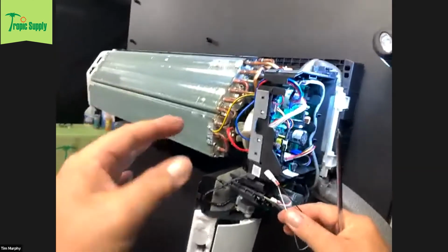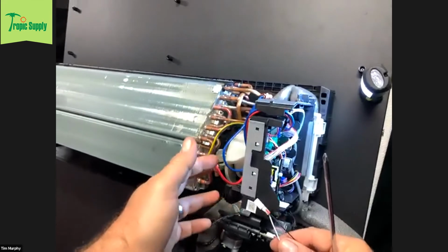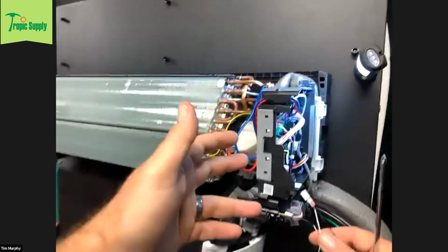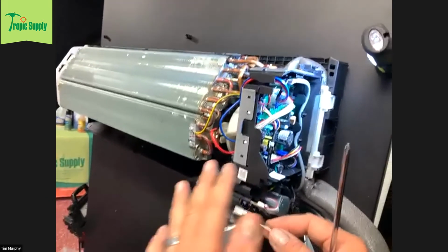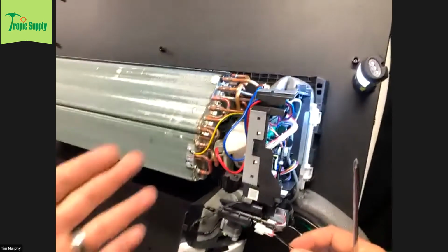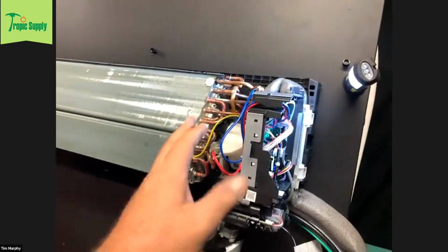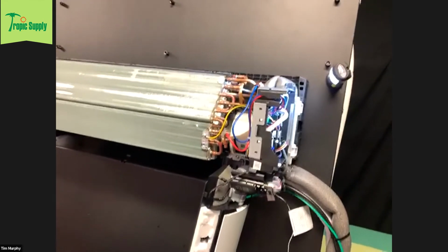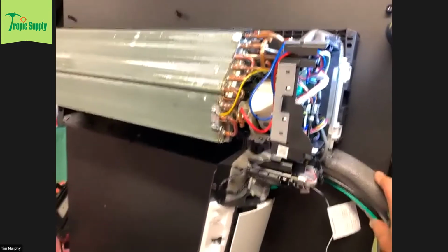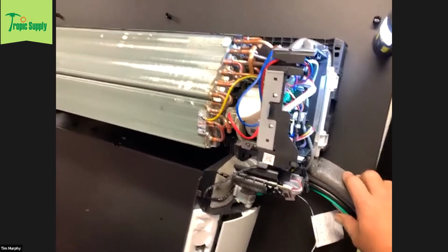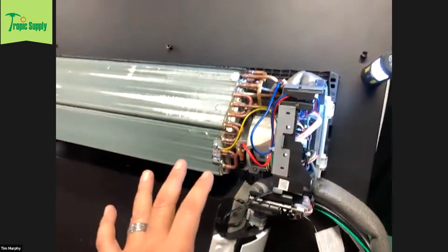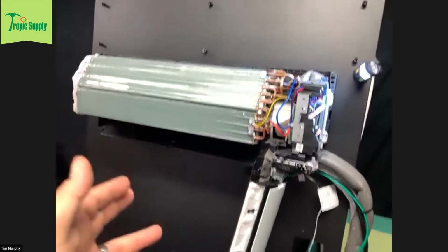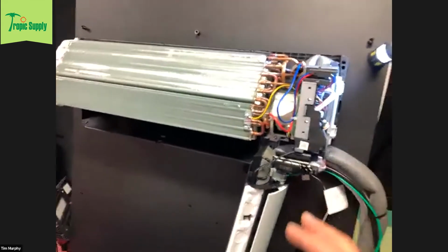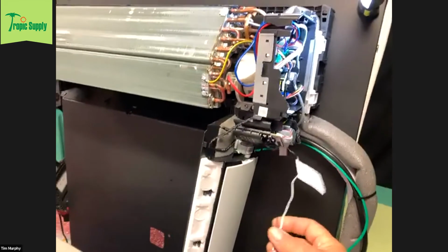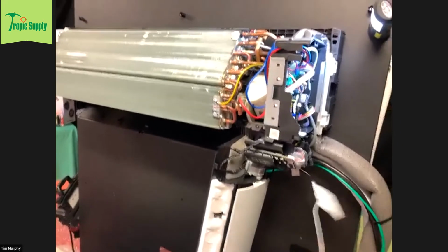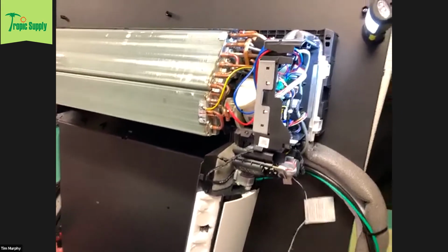What's great about this is that other systems may tell you to break the return air temperature sensor. When you get an error code, you'll get a sensor code or some kind of communication error code. This, if you get an overflow situation, will point you in the right direction. As a technician, you'll know you have an overflow error or a drain line error. If you go to another mini split system that you didn't install, not a Samsung, and you get a communication error, typically tech support is going to tell you to look at the communication wire or look for power in different areas. So a simple float switch install on a lot of other systems could cause a headache of a service call for a technician who hasn't been trained on these systems. What's great about Samsung, by using this way of hooking up the overflow safety switch, is that it points the technician in the right direction, so you're not spending hours diagnosing a communication error when it was just an overflow safety switch the whole time. That's super cool, that's what I really like about it.